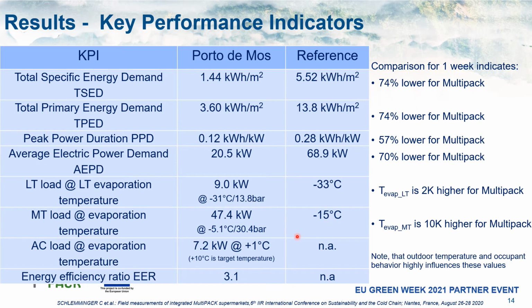And for the AC, we see that the MultiPACK is delivering about 7.2 kilowatt at the evaporation of 1. Here we see also still a bit of improvement potential for the MultiPACK side, because the desired evaporation temperature in the air handling unit is 10 degrees C. If we look at the energy efficiency ratio for this period, we see that the MultiPACK side has an energy efficiency ratio of 3.1.